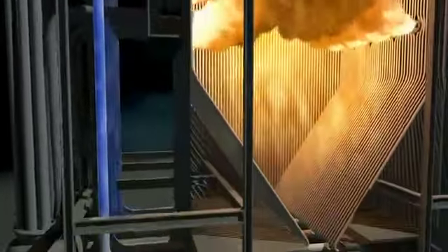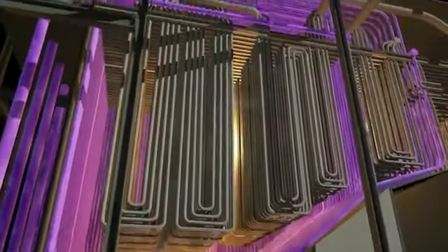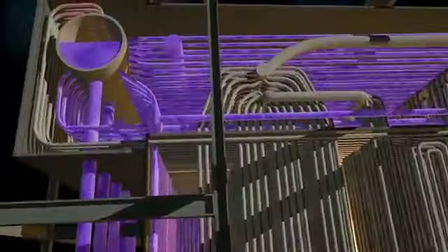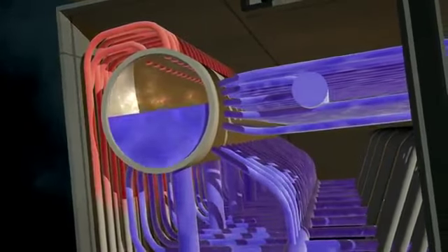Liquid water flows through a large tank and into the base of the firebox. A network of 2-inch tubes line the firebox walls, and burners force feed a continuous supply of combustible fuel into the ultra-hot firebox. Eventually, the insides of the firebox burn so hot that its surrounding steel walls would melt if not for the tube-lined walls of liquid water. At the point in the cycle when the liquid water turns to steam, the steam separates and collects at the top of the steam drum.